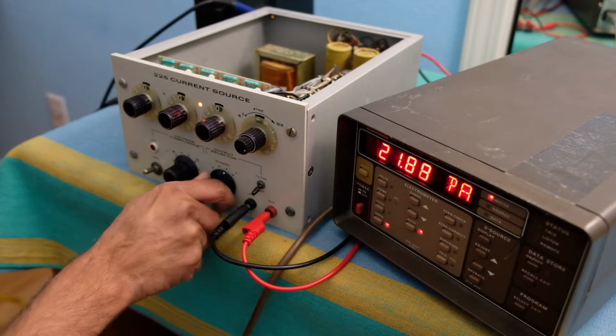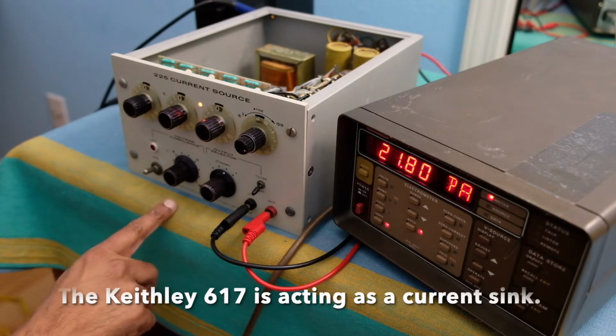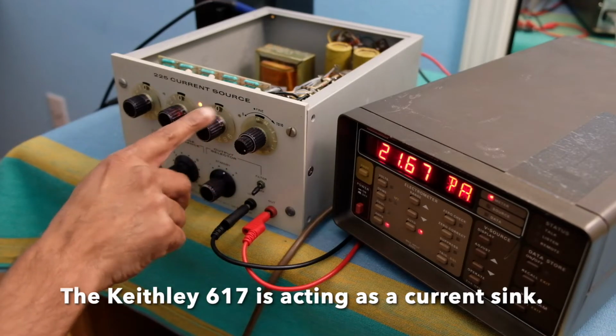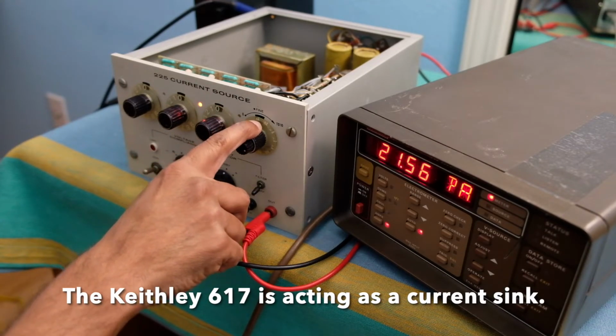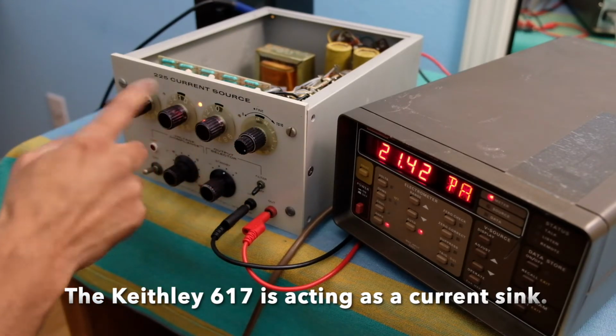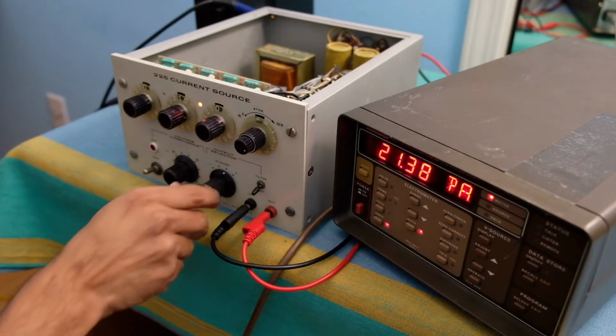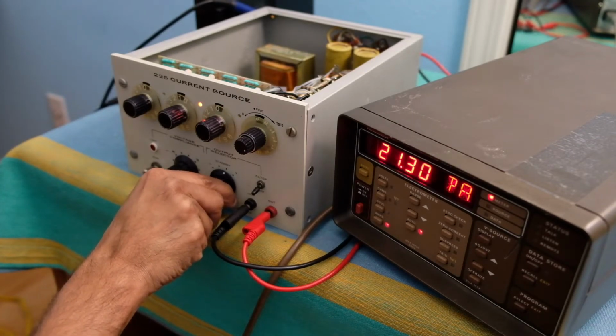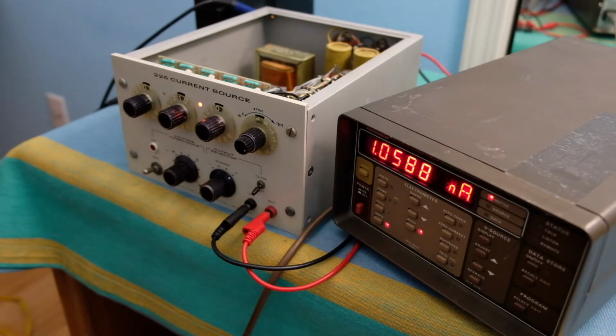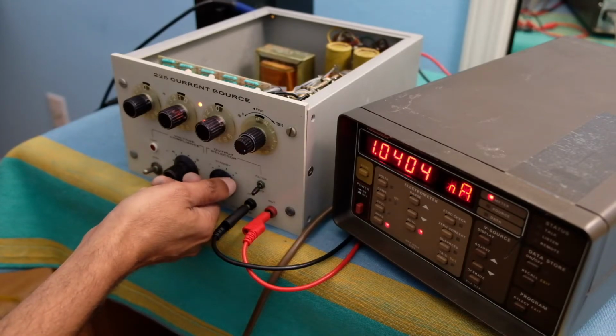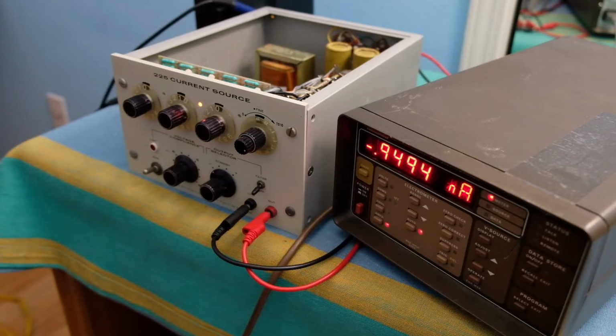So right now the machine is in standby mode. Nothing has been selected here. So let's go to the lowest scale, which is the nanoamp scale, 1 nanoamp. I don't want to go too low because the setup is not good enough to measure in picoamps without too much noise interference. So this is plus 1 nanoamp, and it's not too bad. It's 1.05, 1.06 in that neighborhood. Plus the negative side, yeah, it's minus 0.95. That shows there is an offset which can probably be removed, but I have to see all the different ranges to see how that works out.